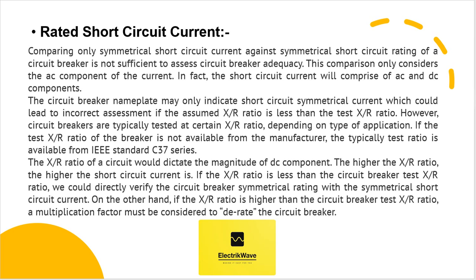Comparing only symmetrical short circuit current against the symmetrical short circuit rating of a circuit breaker is not sufficient to assess circuit breaker adequacy. This comparison only considers the AC component of the current. In fact, the short circuit current will comprise both AC and DC components. The circuit breaker nameplate may only indicate short circuit symmetrical current, which could lead to incorrect assessment if the assumed X by R ratio is less than the test X by R ratio.